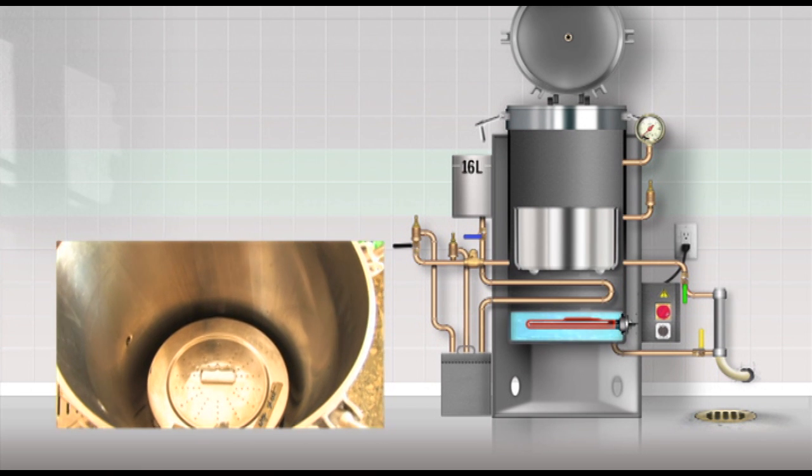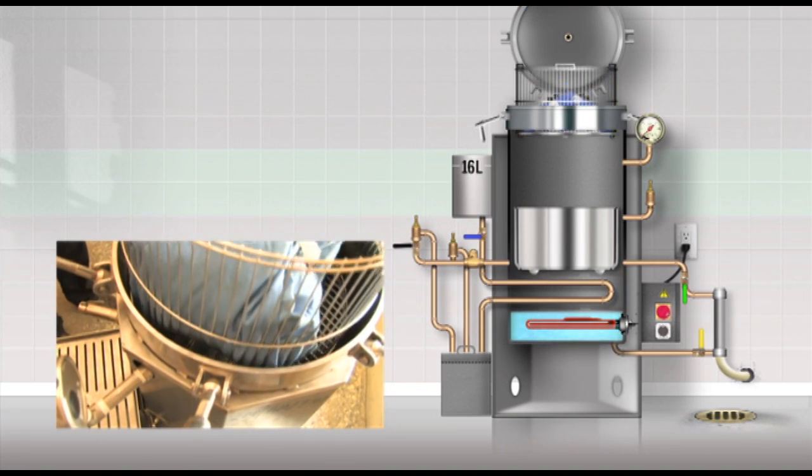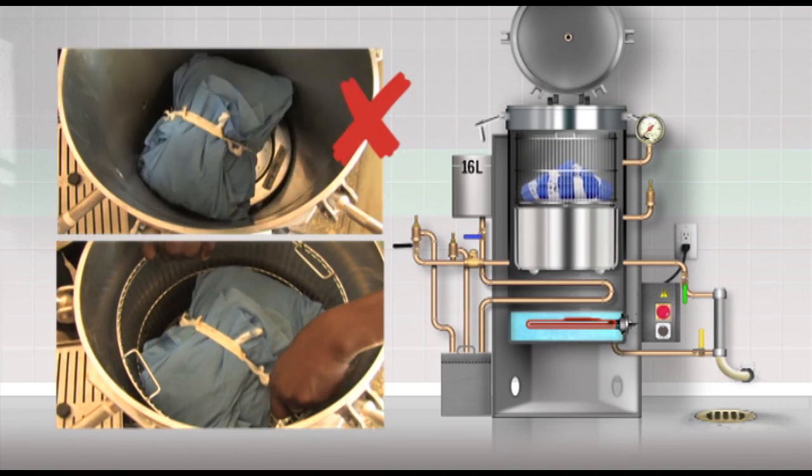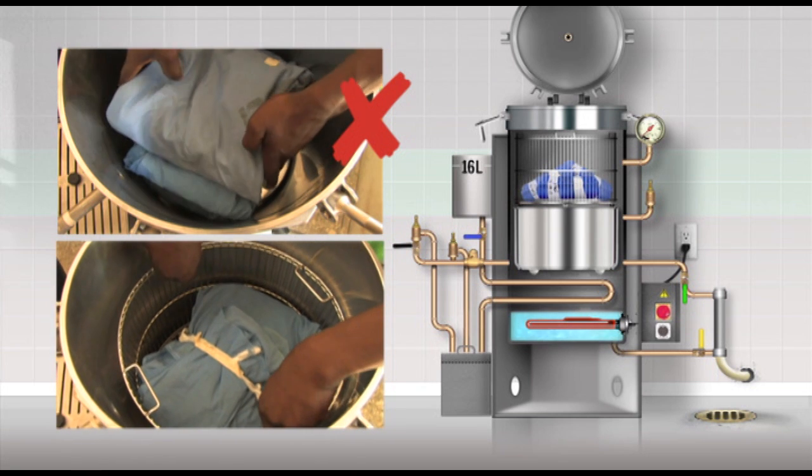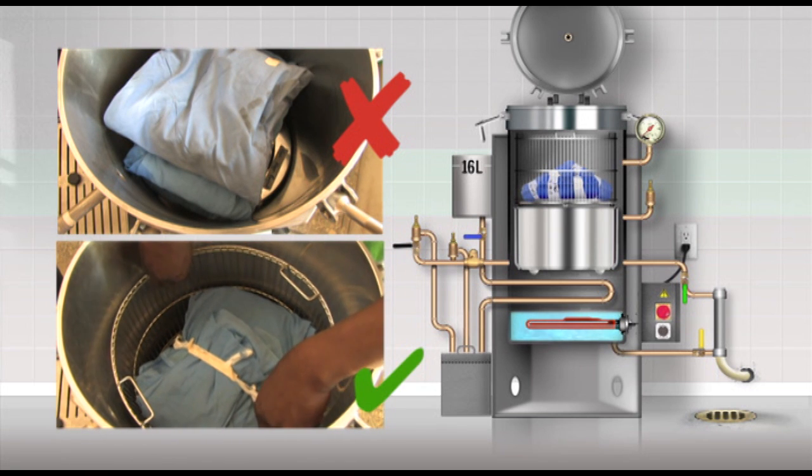It should not be overloaded as the steam has to be able to move freely and penetrate each pack. The pack should not touch the chamber wall, so use grid baskets or drums.